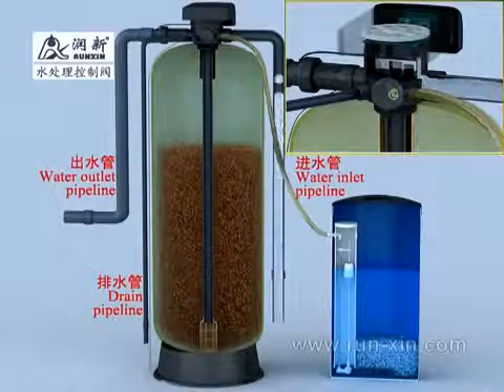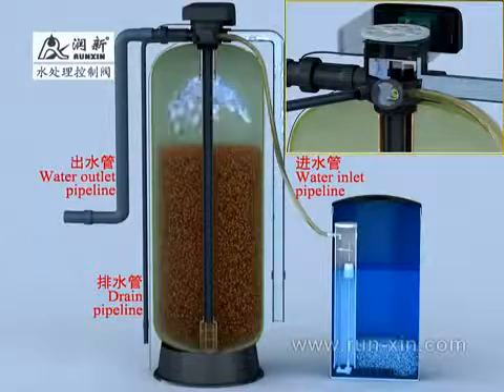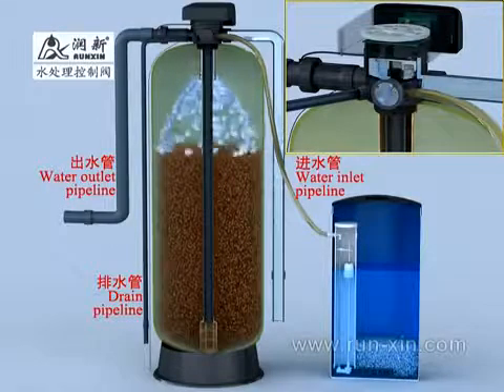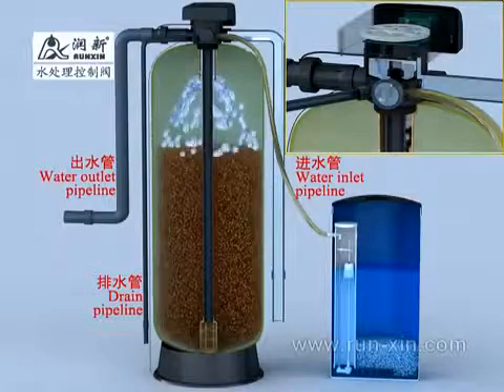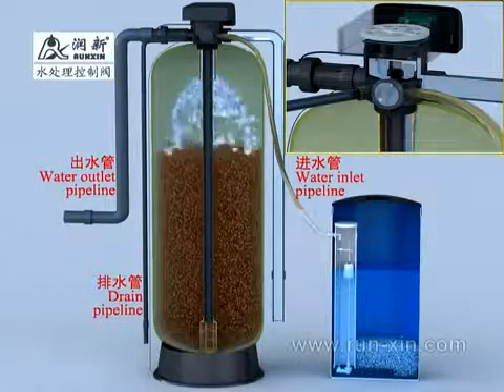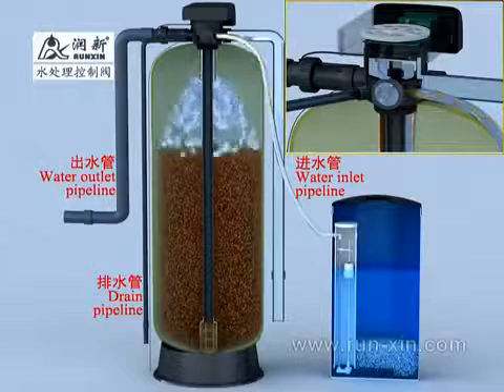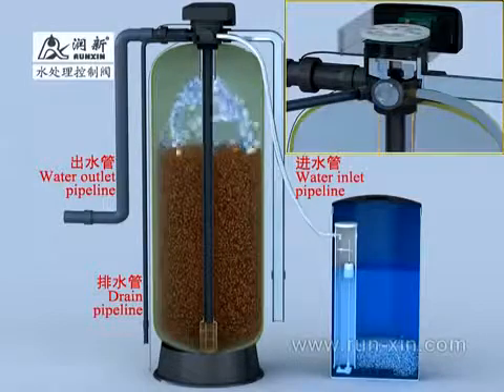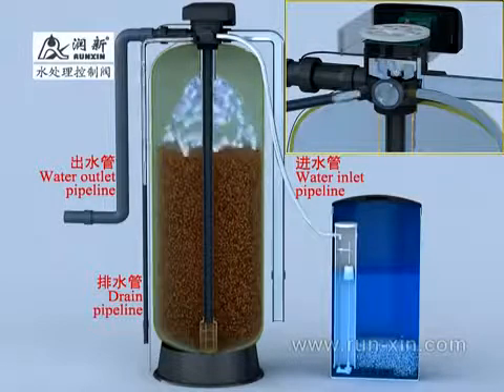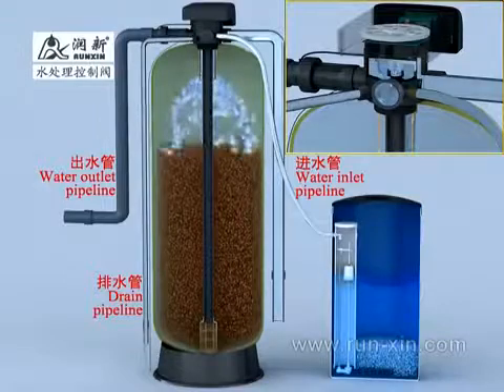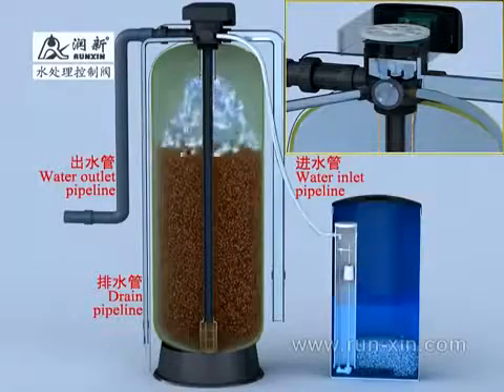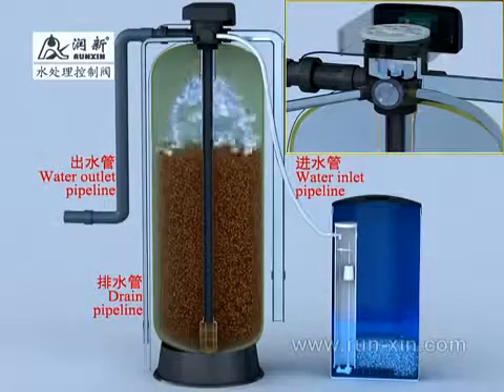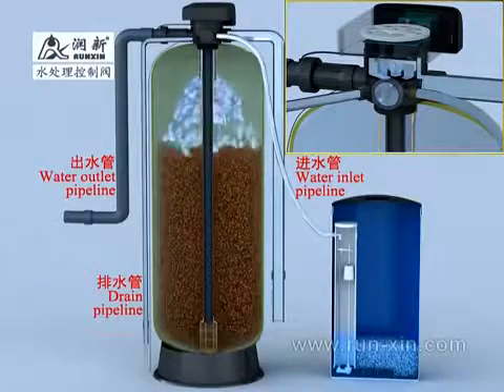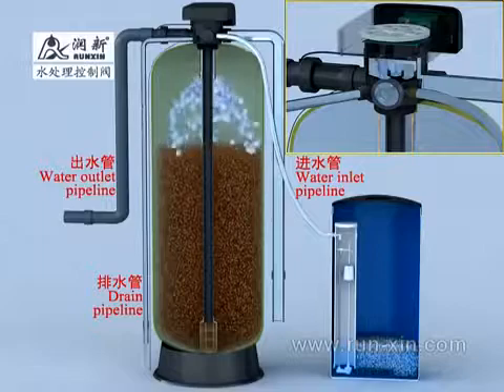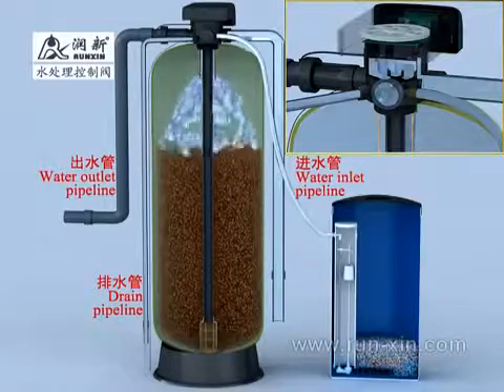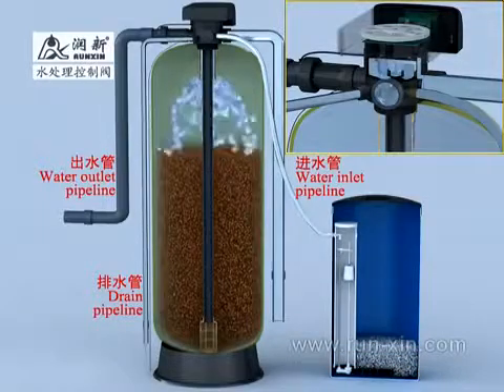Raw water flows into the control valve through the water inlet, passes the valve core to the injector inlet, and flows quickly to the injector outlet, which produces a vacuum under pressure, so that the brine is sucked from the brine tank through the brine line connector to the valve, then to the tank. The brine goes down through the resin layer, through the bottom strainer to the riser pipe, then upward to the valve body, valve core, and finally flows out from the drain outlet.